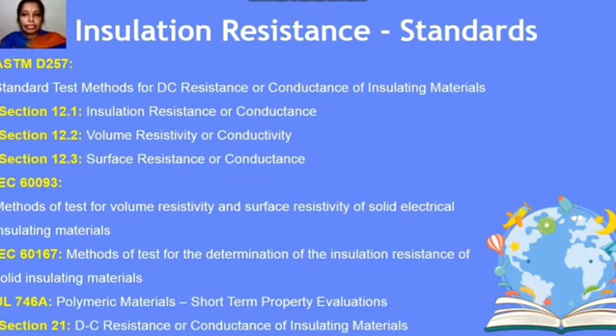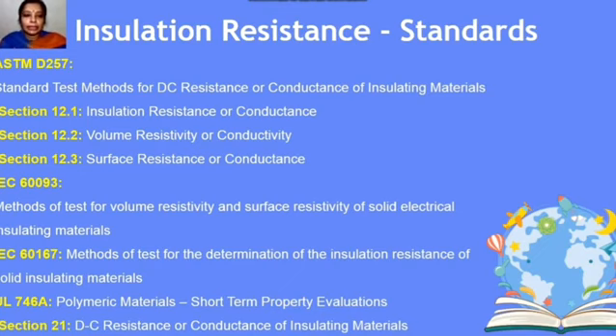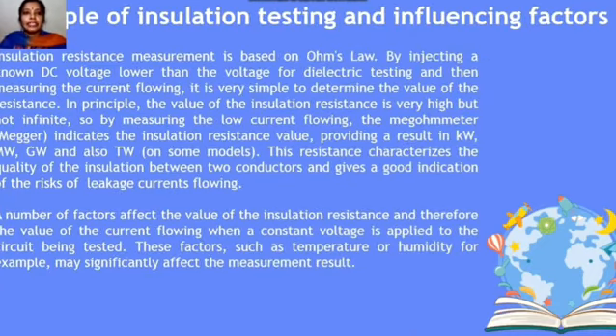Relevant standards include the standard test method for DC resistance or conductance of insulating material: sections 12.1 resistance and conductance, 12.2 volume resistivity and conductivity, 12.3 surface resistance and conductance. IEC 60093 deals with volume resistivity and surface resistivity of solid dielectric materials. IEC 60167 covers determination of insulation resistance of solid insulating material. UL 746A covers polymeric materials short-term property evaluation, section 21, DC resistance or conductance of insulating materials.